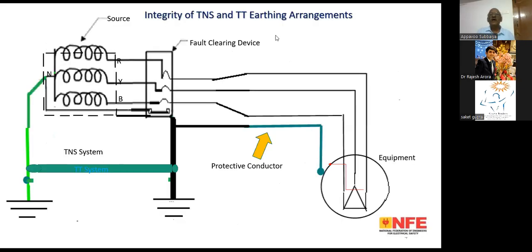So before explaining these aspects, I would like to touch upon the earthing system, because people are confusing the earthing protocol with what the IS and IEC say. There is much confusion as far as the LT supply installations are concerned, and the general earthing arrangement. There are only three types. One is TN-S, the TN, and the TT. This is the TN-S system.